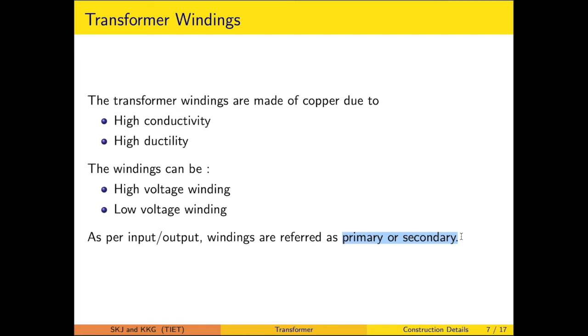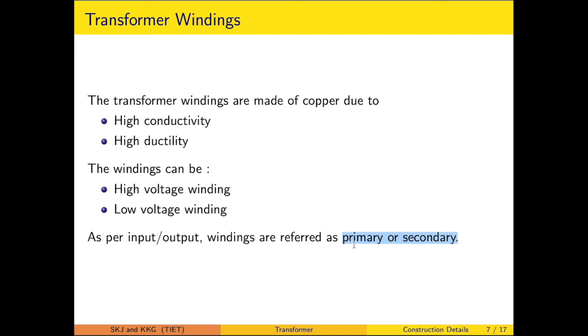These windings can be regarded as the high voltage winding or the low voltage winding. As the name suggests, the high voltage winding has the higher voltage level, and the corresponding current level will be low. So the high voltage winding is made of thin conductors but a large number of turns. Correspondingly, the low voltage winding is made of thick conductors and a lower number of turns. We sometimes refer to the windings as primary or secondary, but there is no restriction that the high voltage winding be referred to as primary or secondary, or similarly for the low voltage winding. The primary and secondary terms we sometimes use while dealing with the analysis of the transformer. Otherwise, in practical cases, they are referred to as the high voltage and low voltage windings.